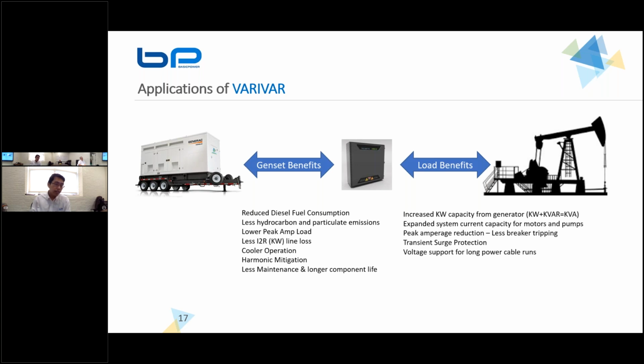Now, this can lead to less hydrocarbon particulate emissions, and it lowers the amount of peak amps inside your generator. What that means is because we're reducing the amount of current you require to operate the same exact load, you can have more space to put in new equipment if you need to. The problem with power factor is that if you happen to have a lot of amps put onto the same generator, and they're all running on poor power factor, you're missing out on that additional space that you could use if you optimize the power factor itself.